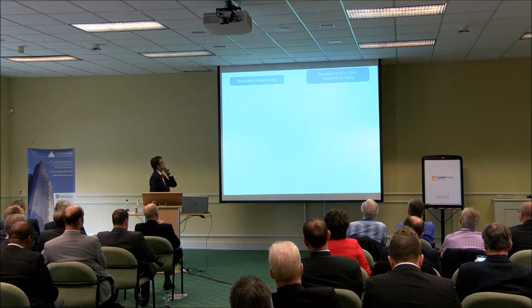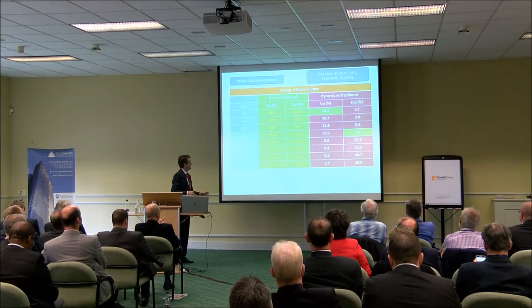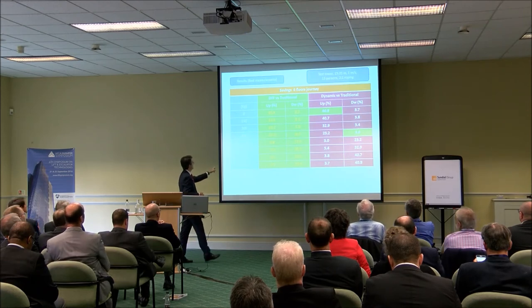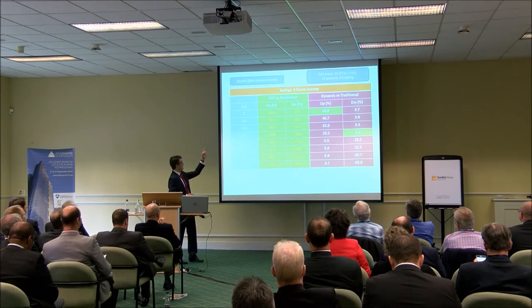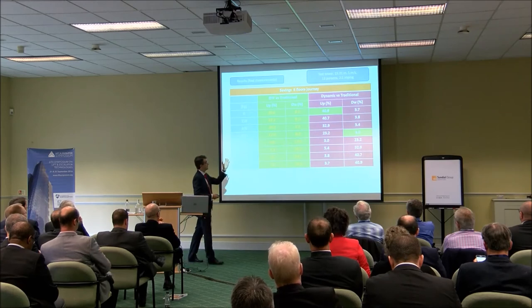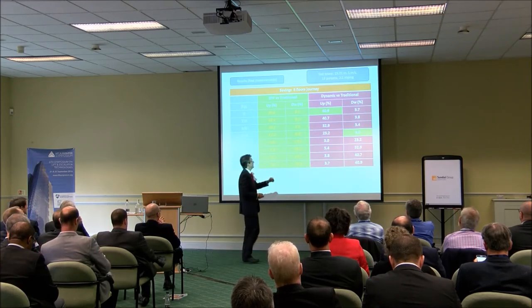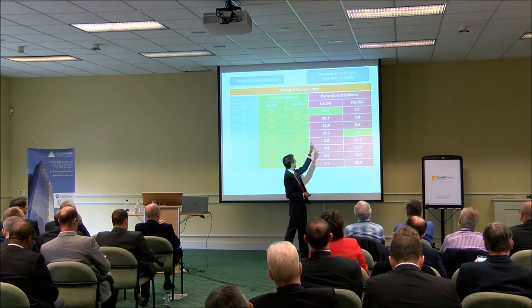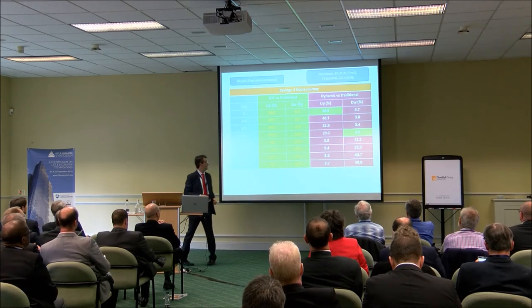Here we have real results from our test tower. On the vertical axis we have different loads, from empty car to full load. In orange we can see the savings for a journey of six floors distance, which is approximately 15 meters. The savings identified range from 3% up to 41% depending on load conditions.